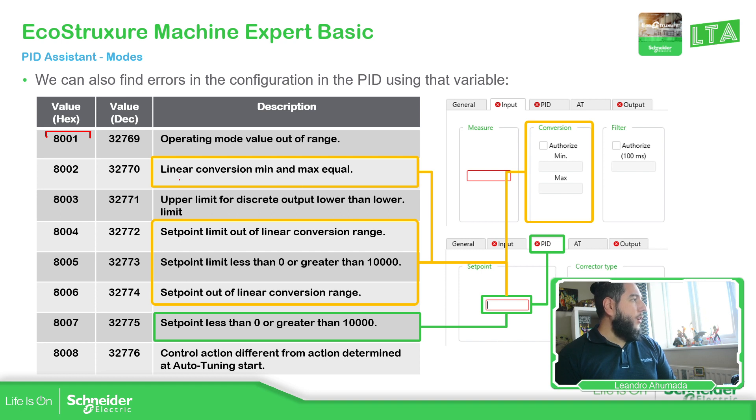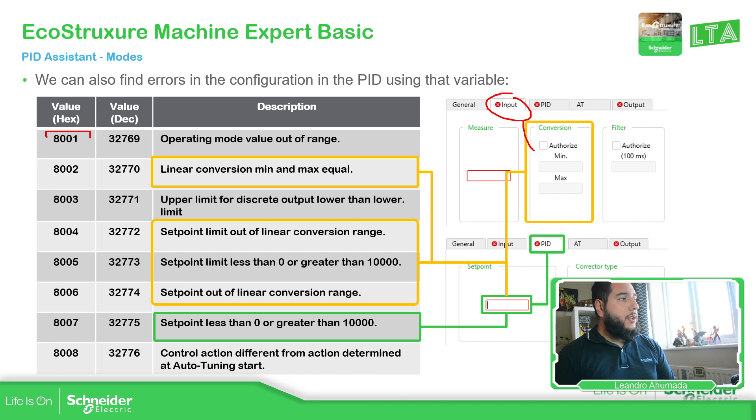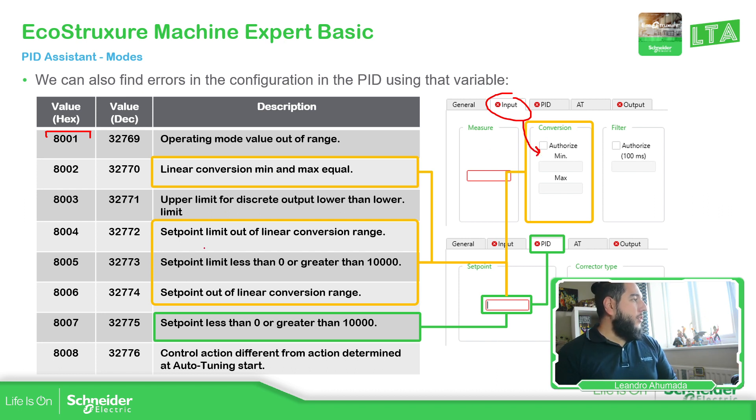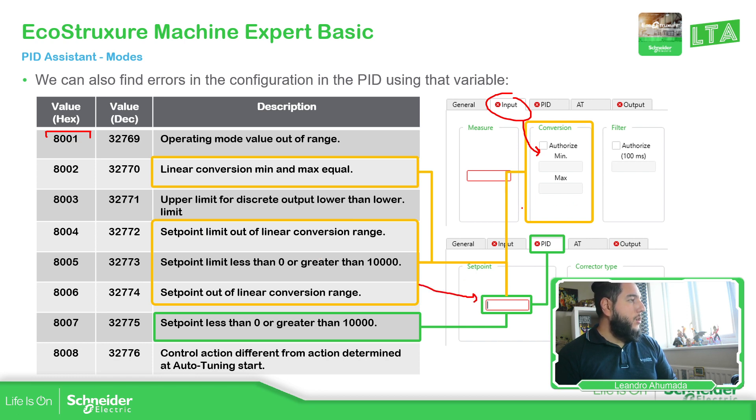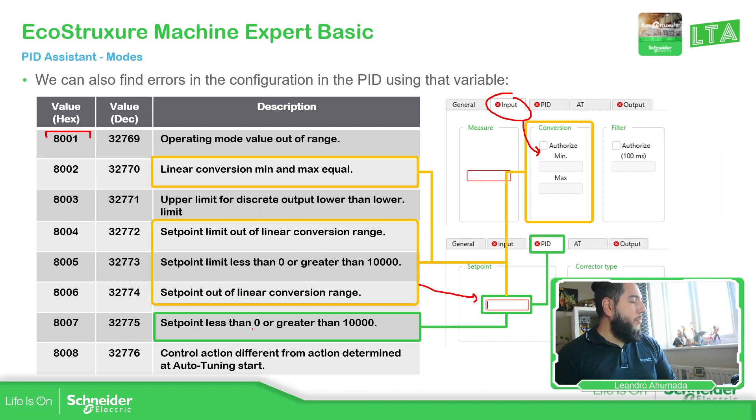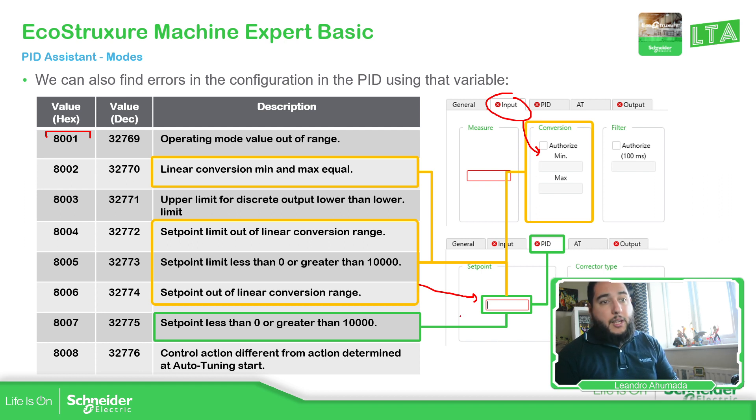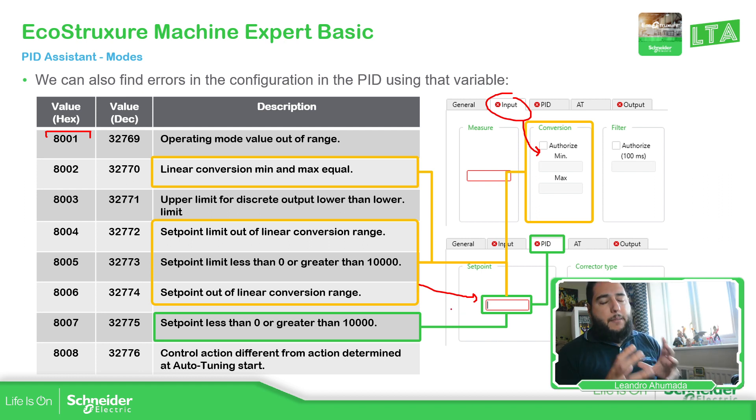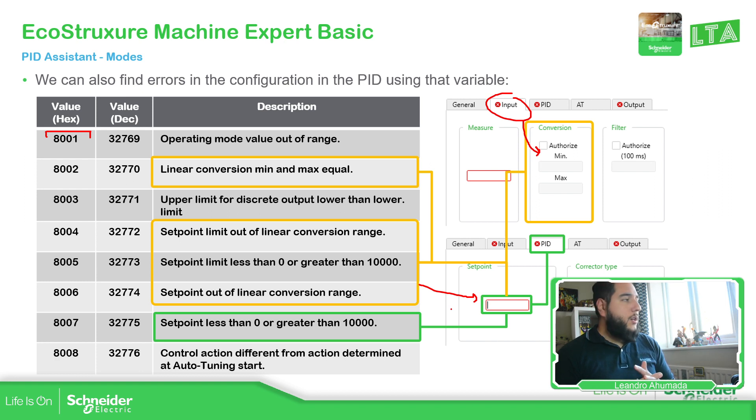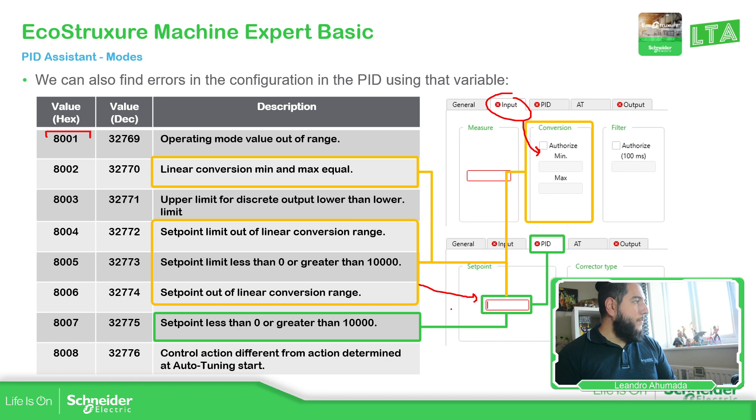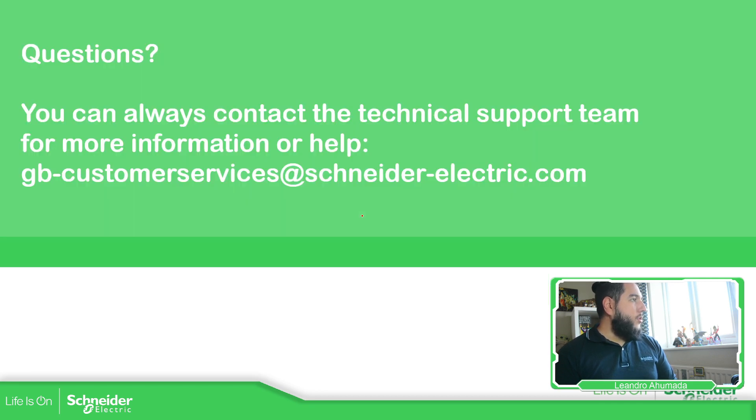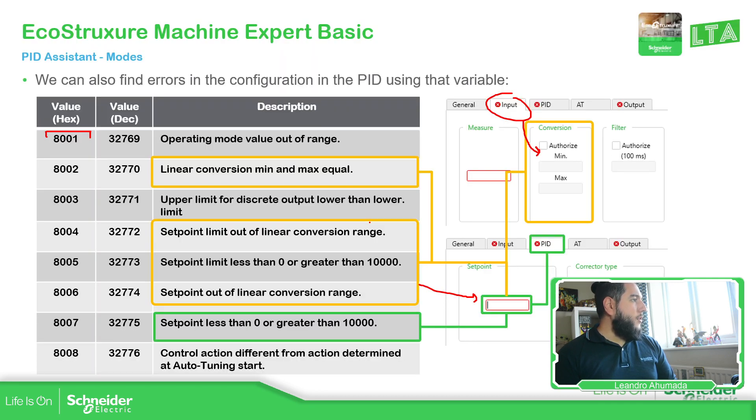For example, is indication where to find the error. Or what is linked to it, for example, linear conversion, min and max are equal. Here is the conversion in the input, but if it's not authorized, then there's nothing to do. Then you have, for example, the set point limit that is going to be linked also with this part. And then you have also the set point less than zero or greater that is linked to the set point. So that value can tell you if you have an issue on the configuration.